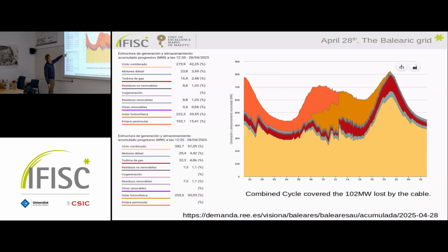Combined cycle went from 279 to 382. It took the 100 megawatts, and that's it. I may be wrong, it might just be a coincidence, but it's clear that having a fast response isn't the cause of the trouble—this is about when there is trouble, how you cope with that.